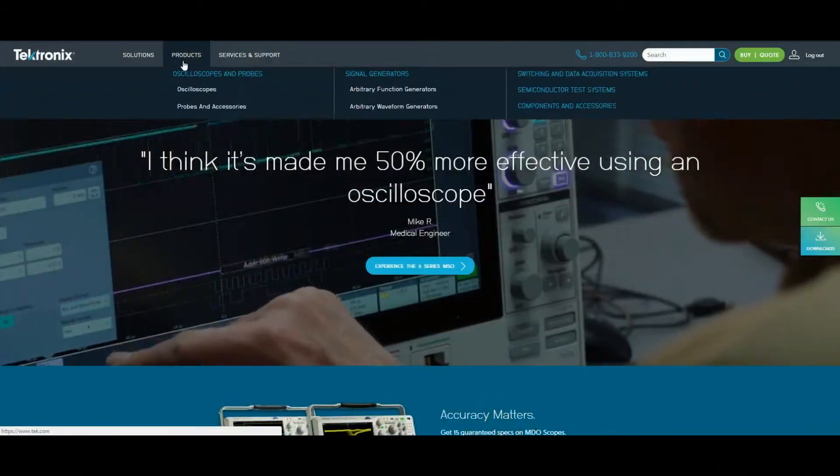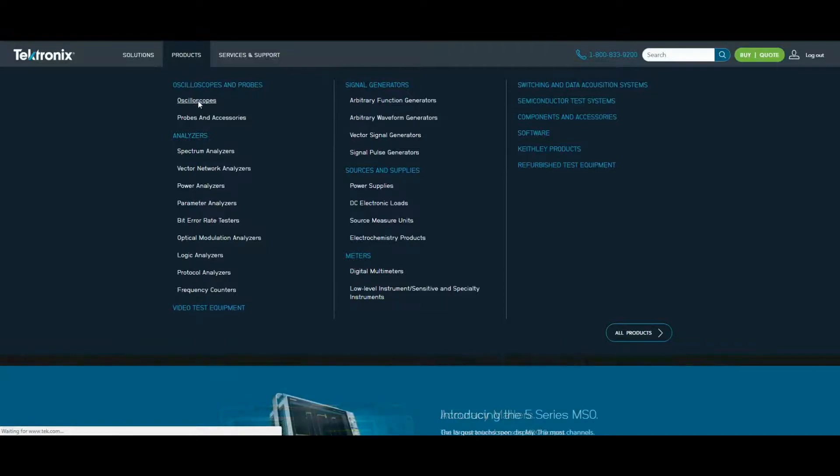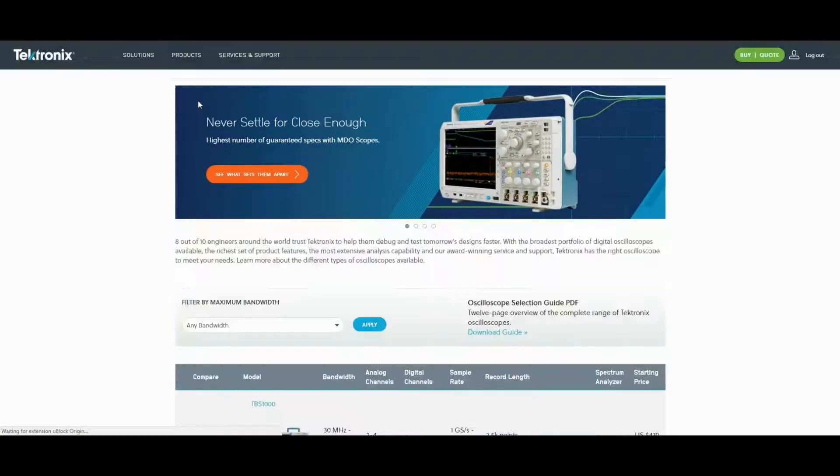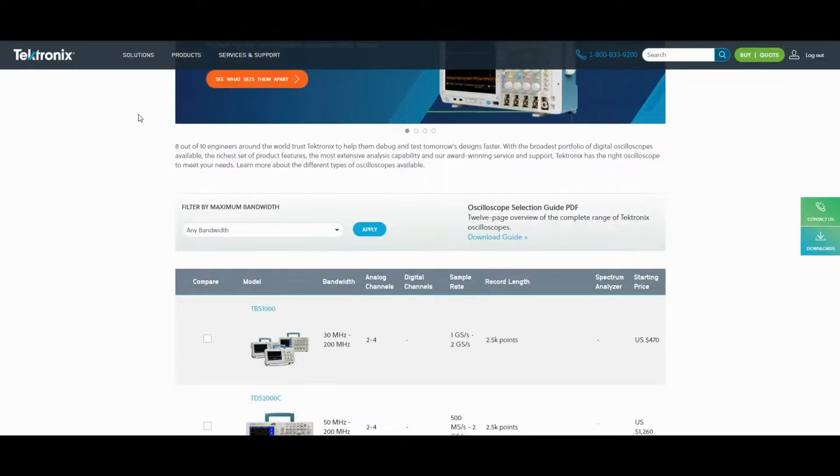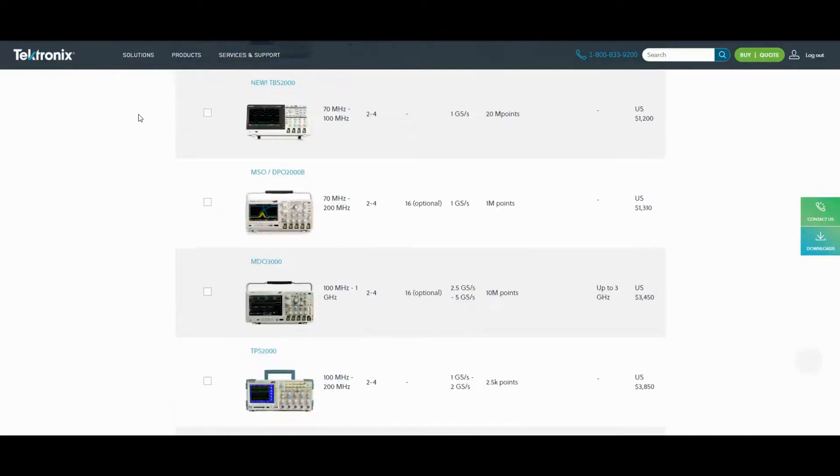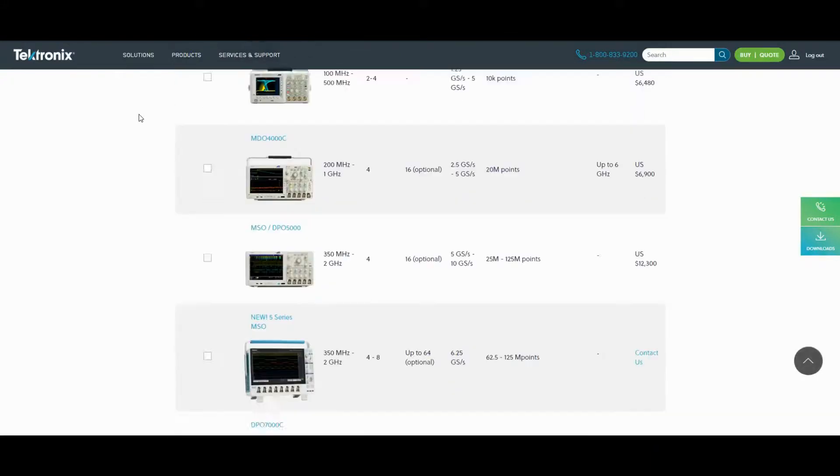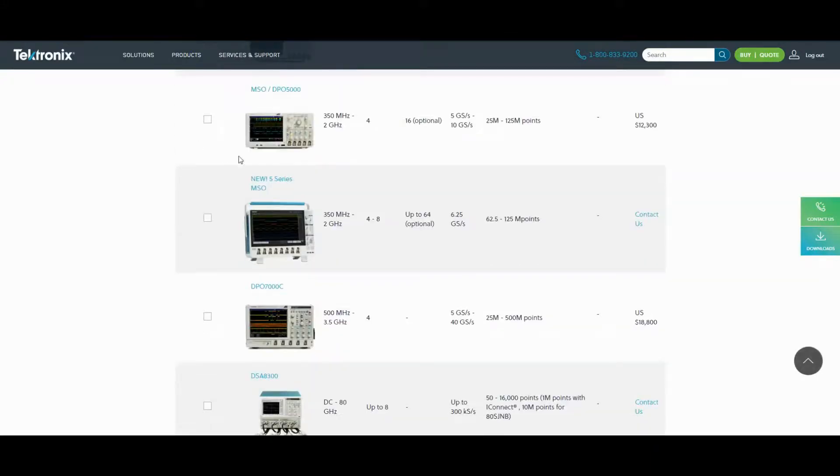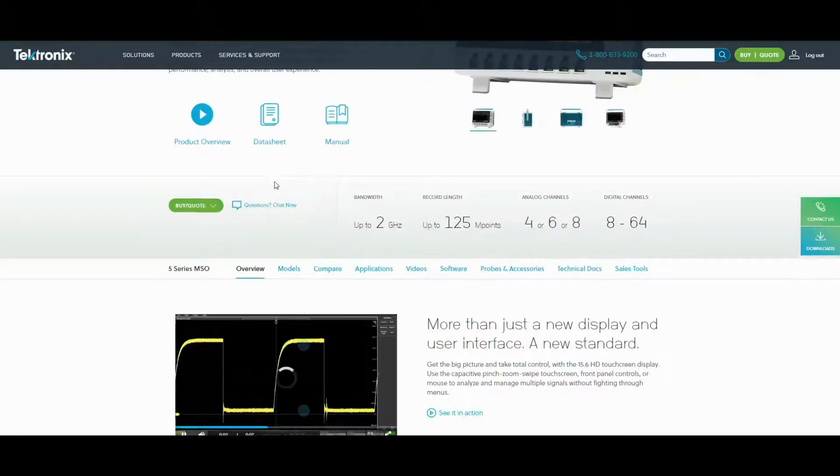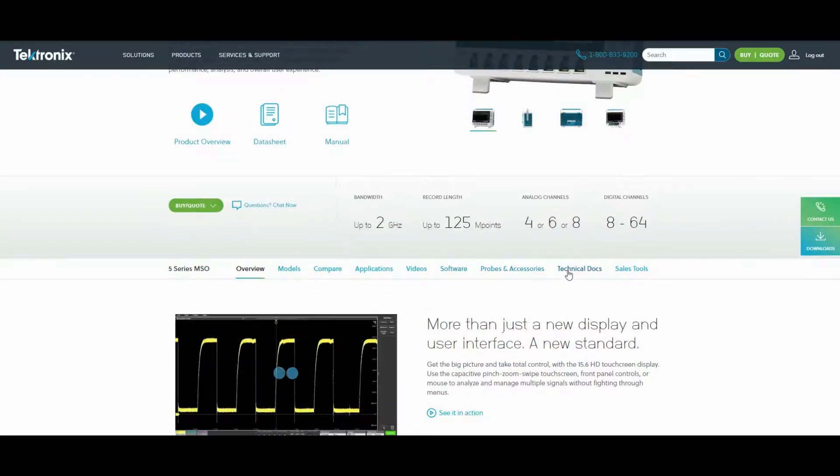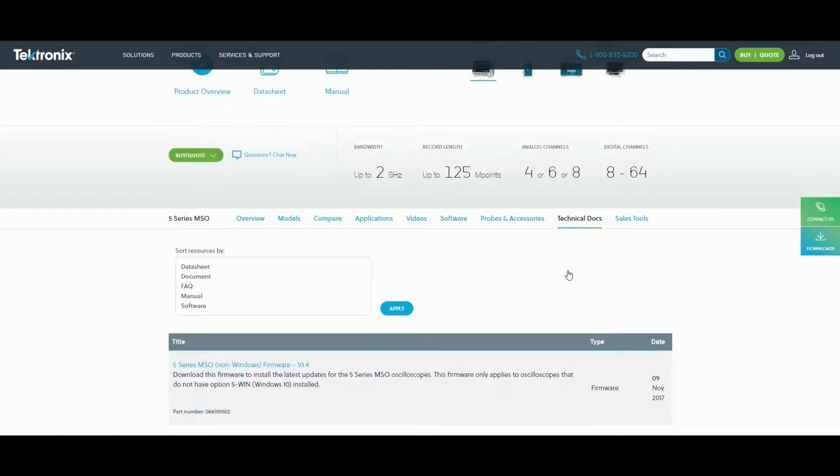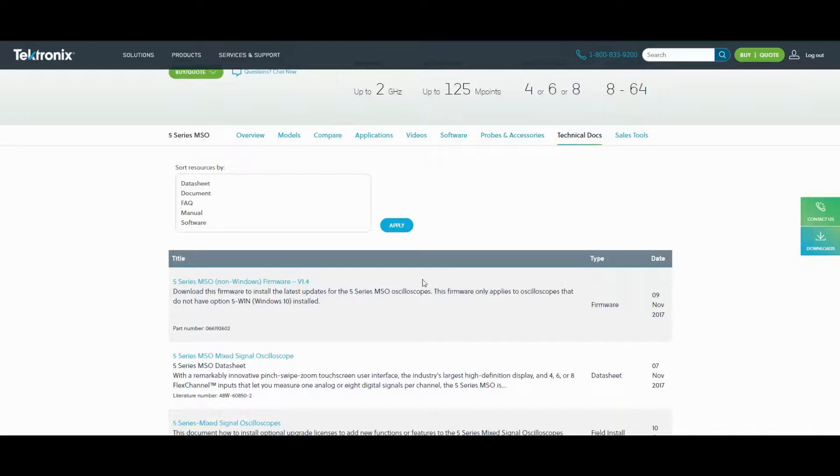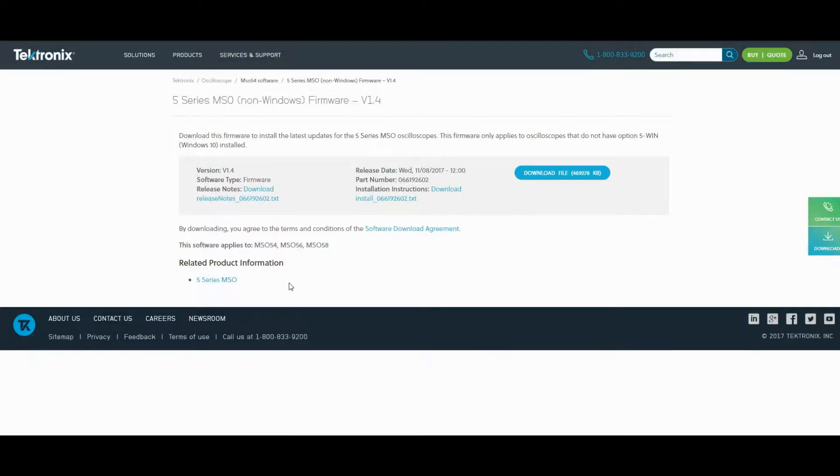Here's where you can find the firmware download. Go to tek.com and click Products, then Oscilloscopes. Scroll down to the 5-series MSO and select it. On the next page, go to the Technical Docs tab. You can filter this list to show software, but the firmware update should be listed near the top. Make sure you're logged into your tek.com account, then click the download button.